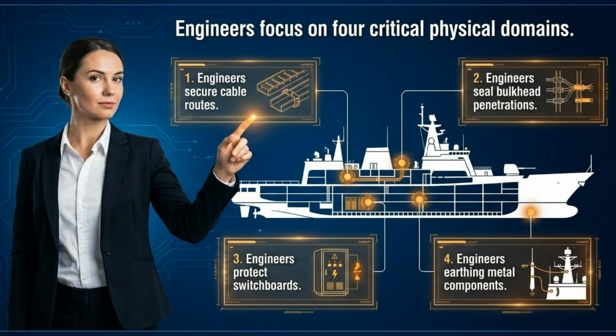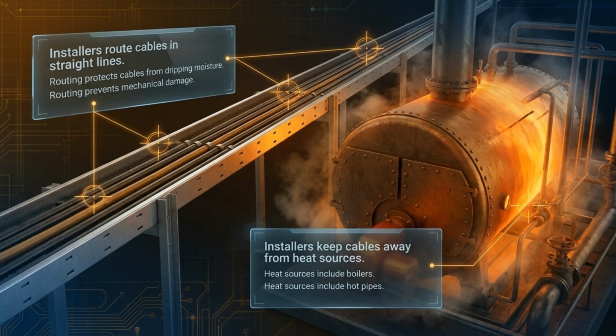the ship. To achieve these goals, engineers focus on four critical physical domains: securing cable routes, sealing bulkhead penetrations, protecting switchboards, and effectively earthing all metal components. When routing cables, installers must ensure they are laid in straight lines to protect against moisture and mechanical damage. Furthermore, cables must be kept away from heat sources like boilers and hot pipes.